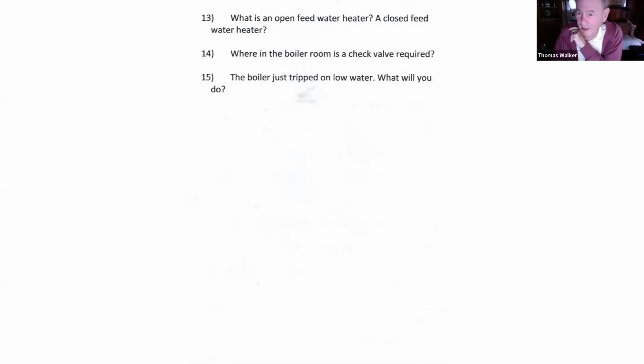All right. Guess what they're looking for when they ask that question? They don't want you to do what? Just add water. They don't want you to panic. They don't want you to call for help. All right. They want you to look at it logically, calmly, without panic and say, I will troubleshoot the cause of the low water, fix it if I am able, and then restart the boiler. Typically, what might happen? Well, maybe the feed pump tripped. If the feed pump tripped because the breaker tripped, is that a pretty easy fix?